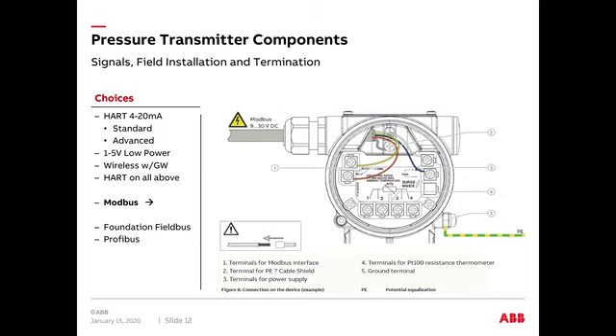All of the above have HART communication as well. The picture shown here is the Modbus. Modbus digital communication is popular depending on the industry. This one shown has clear wiring instructions where you'll see where to put your power and communication lines. This one is for a Modbus multivariable, so it also shows wiring instructions for the RTD you'd be hooking up. With ABB pressure transmitters, you'll see very clear graphics of what you need to do as far as wiring. Some industries also use Foundation Fieldbus and Profibus. So these are some examples of the different types of signals you'll be running into.